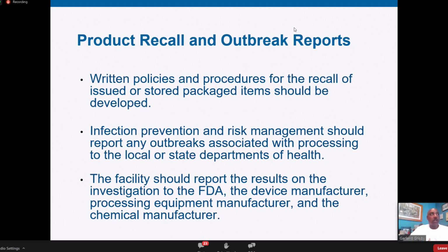See, this is where we talked earlier about the MAUDE database, which we'll get into on a slide shortly. But the device manufacturer needs to be notified, the equipment manufacturer, and the chemical manufacturer. This is how we get those reports in our facilities about a recall. And so they'll spell out exactly what we need to do and let them know if we have this particular product or if we use this particular product. Because there have been situations where there's a recall out there, but we may not have this particular scope or this piece of equipment anymore, and the information wasn't updated. So we need to have this in our policies. Slide.